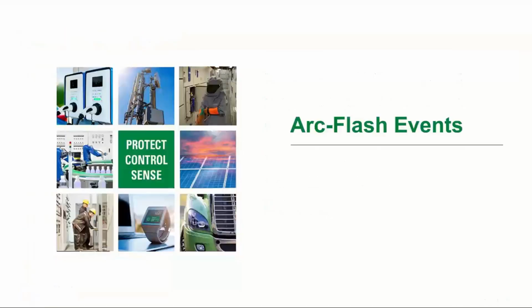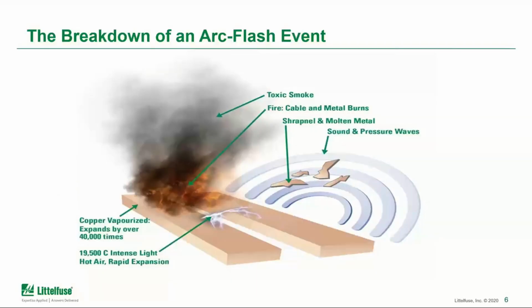So let's get started. So first, when you break down an arc flash event, it's a release of energy through, typically insulating a conductor. In this case, we're talking about air, between two conductive elements. So really, what that means is that the electricity will break down and pass through the air and create a rapid release of energy. So, when you look at what is happening, there is a release of light along with the heat and energy that's following. And this heat is very extreme. The extreme temperatures you can see on those arc events can be 20,000 degrees Celsius, which if you do the math, can be several times hotter than the actual surface of the sun.